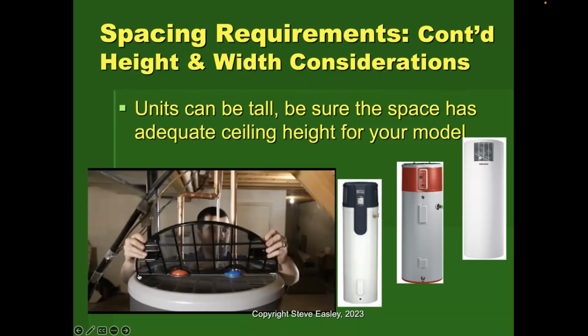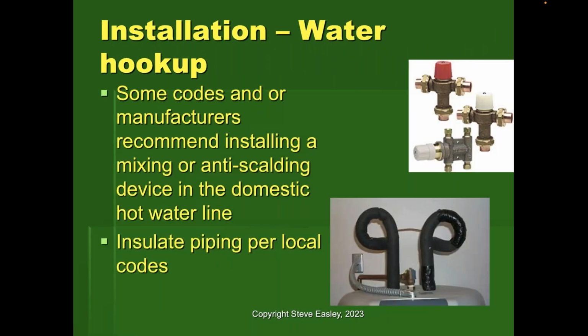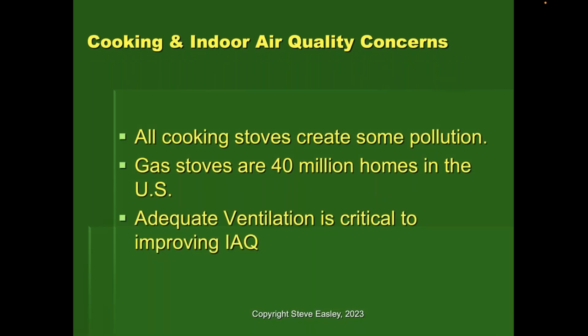If there's adequate room, make sure you have room to change the filters. This is a little air conditioning system, right? It's a heat pump, so it needs to have the capacity to filter the air, so we want to make sure those filters are in fact clean. And make sure that many codes will require anti-scalding devices, so we want to take care of that and insulate the piping according to national codes. Also keep in mind where you place these units, they put out 49 to 64 dB. So if you're concerned about noise, you might not want to put one of these near a bedroom or other noise-sensitive locations. Be cognizant of that. They are obviously going to be a little bit noisier than a traditional water heater.